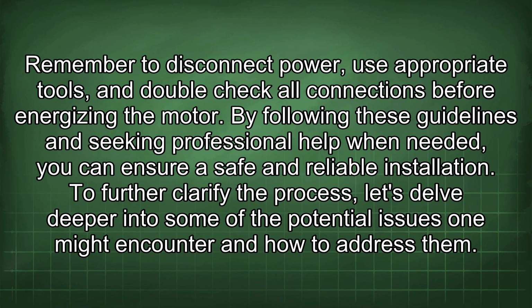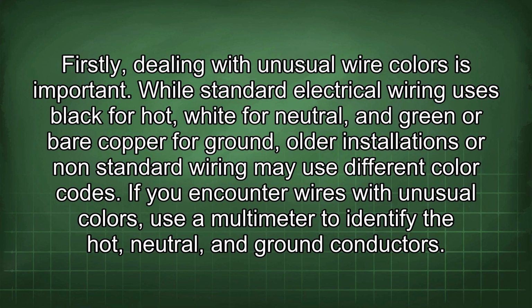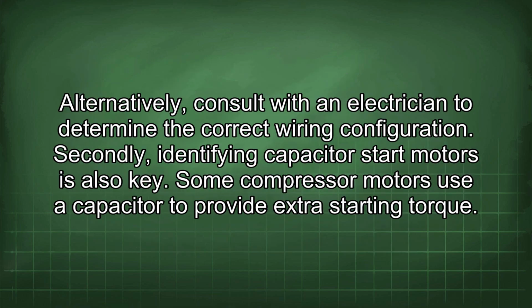To further clarify the process, let's delve deeper into some of the potential issues one might encounter and how to address them. Firstly, dealing with unusual wire colors is important. While standard electrical wiring uses black for hot, white for neutral, and green or bare copper for ground, older installations or non-standard wiring may use different color codes. If you encounter wires with unusual colors, use a multimeter to identify the hot, neutral, and ground conductors. Alternatively, consult with an electrician to determine the correct wiring configuration.